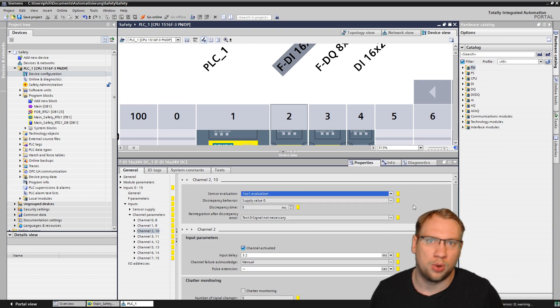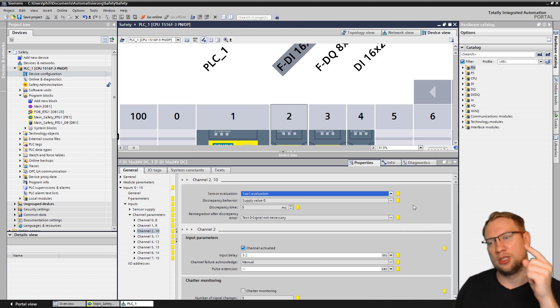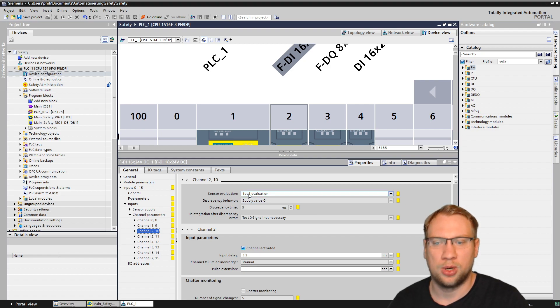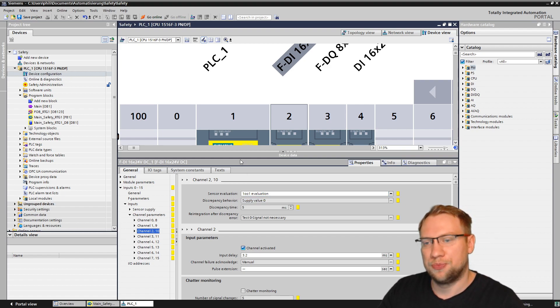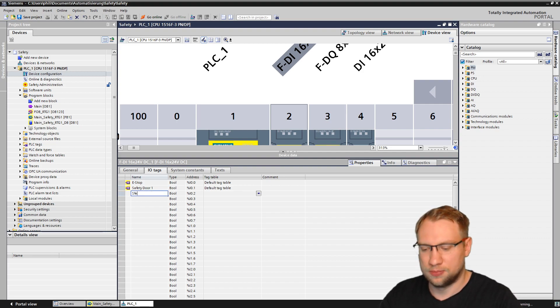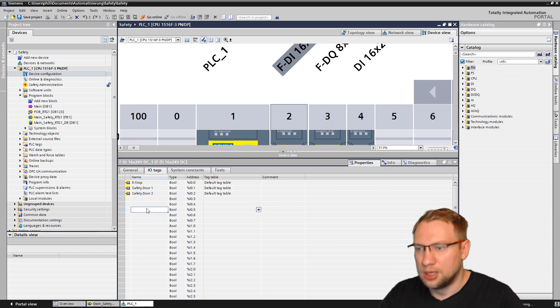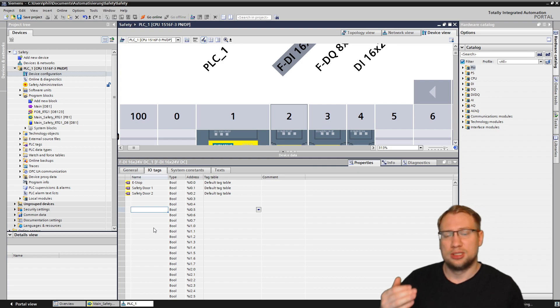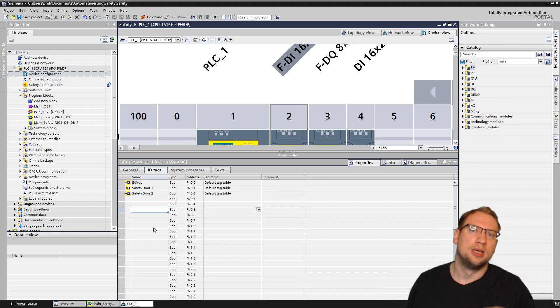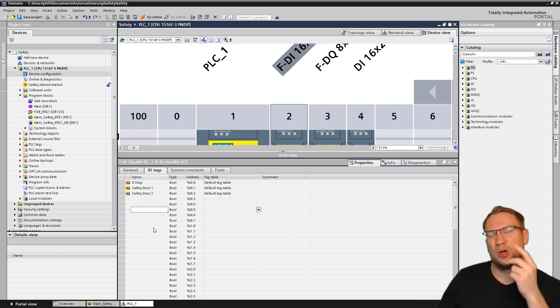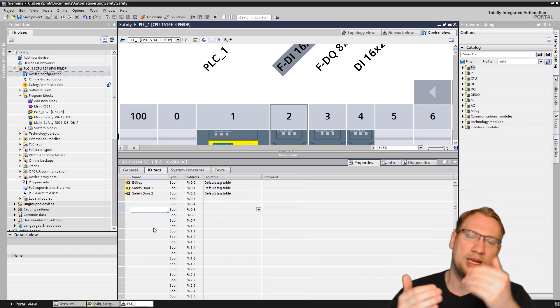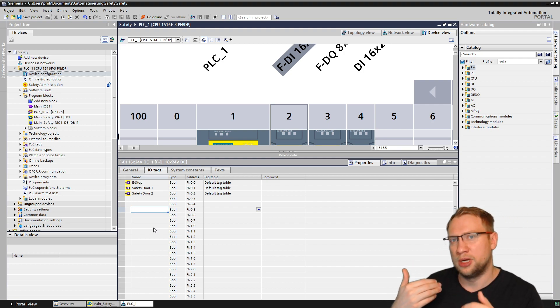I could use one-of-two evaluation or one-of-one — it doesn't really matter. I'll put them both as one-of-one. The door we're connecting has two sensors: one sensor goes into channel one, one goes into channel two, and they both have just one output each, so that means one-of-one. I'll also label these as safety door one and safety door two. Usually one of those sensors is normally closed and one is normally open, meaning one sends a one signal and the other sends a zero signal, so you can evaluate that they have to be different: if the door is open it's zero-one, if the door is closed it's one-zero.